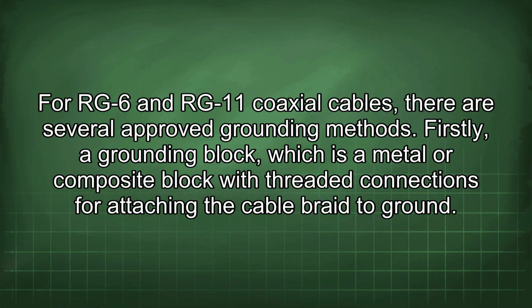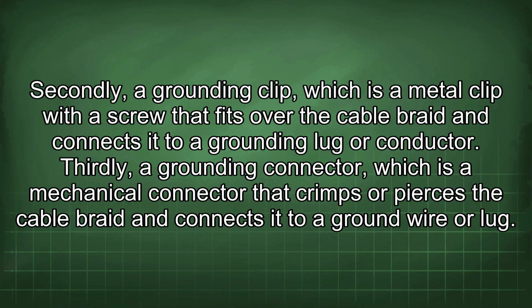For RG-6 and RG-11 coaxial cables, there are several approved grounding methods. Firstly, a grounding block, which is a metal or composite block with threaded connections for attaching the cable braid to ground. Secondly, a grounding clip, which is a metal clip with a screw that fits over the cable braid and connects it to a grounding lug or conductor. Thirdly, a grounding connector, which is a mechanical connector that crimps or pierces the cable braid and connects it to a ground wire or lug.